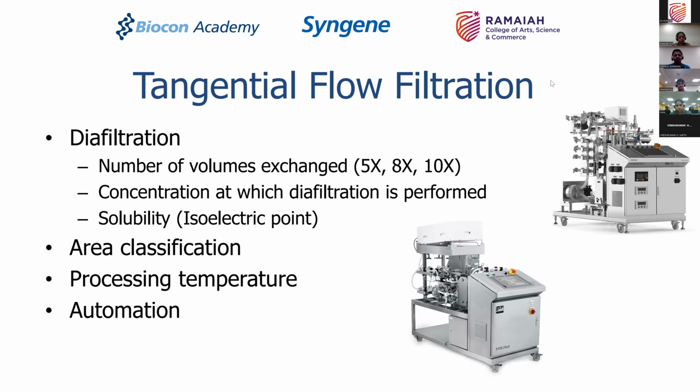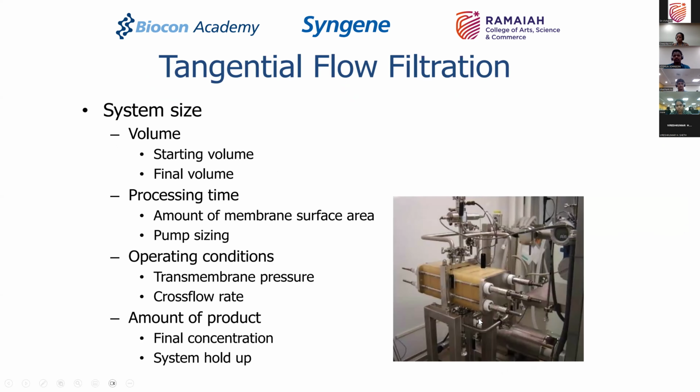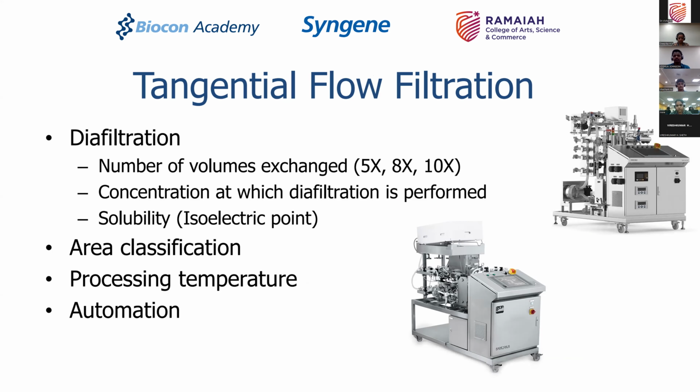So this is how a commercial system looks. The earlier photograph was an old photograph, so I picked out photographs of a modern system. This I think are Sartorius systems. Yes, they are Sartorius systems. So this is somewhere where your membranes will be sitting. The rest of it is the pumping module and measuring the transmembrane pressure and all that, and the control console here, automation.